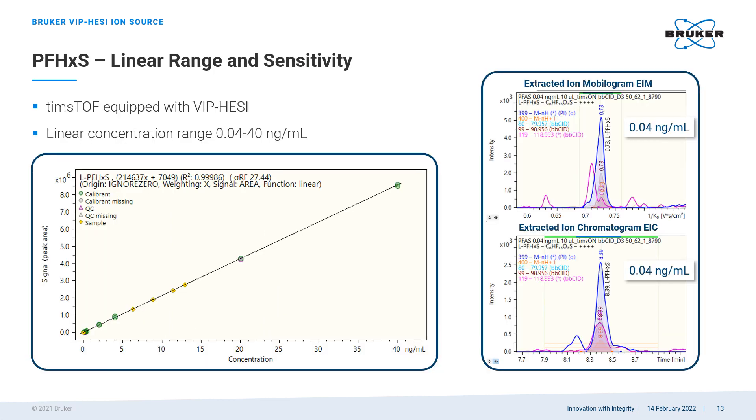The timsTOF instrument with the VIP-HESI ion source also demonstrates very respectable quantitation capabilities. The linearity of the calibration curve and the coefficient of determination are quite excellent over four orders of magnitude of dynamic range. Both the extracted ion chromatogram and the extracted ion mobilogram on the right are very clear and show good signal-to-noise ratio at the lowest point of the calibration curve.